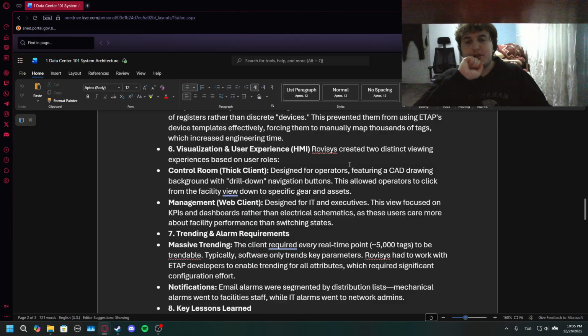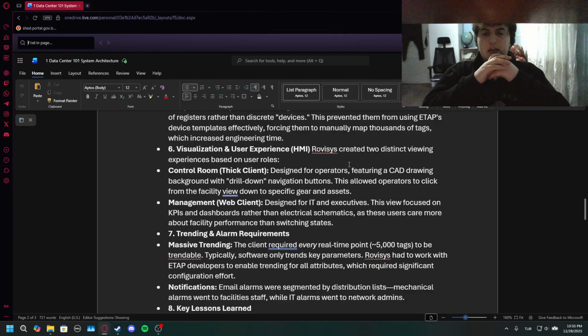Trending and alarm requirements, massive trending. The client required every real-time point, around 5,000 tags, to be trendable. Typically, software only trends key parameters. Rovisys had to work with ETAP developers to enable trending for all attributes, which requires significant configuration effort.